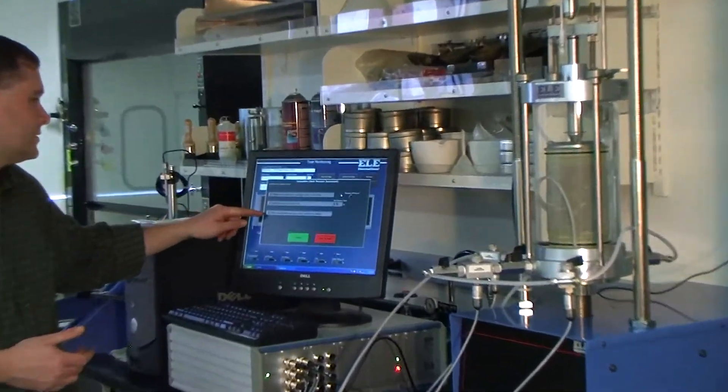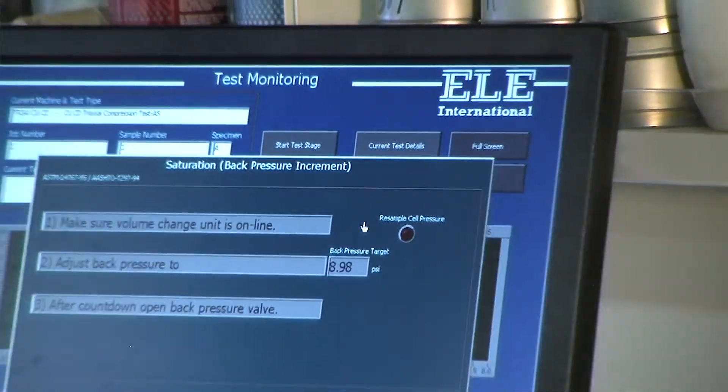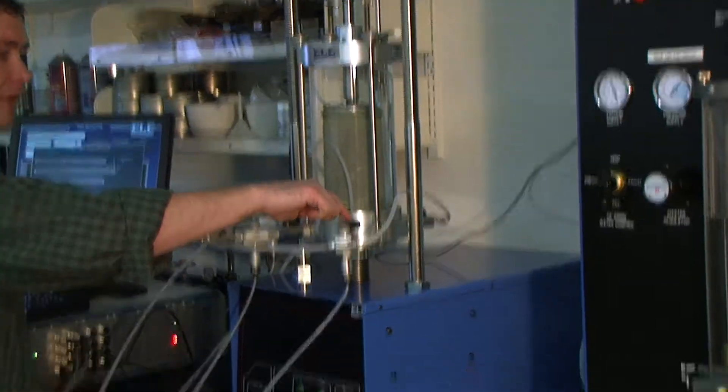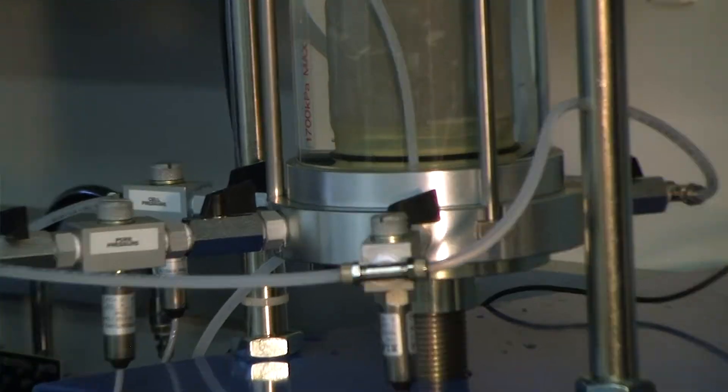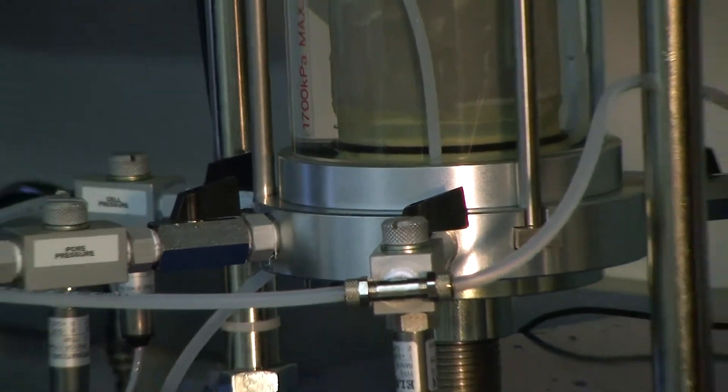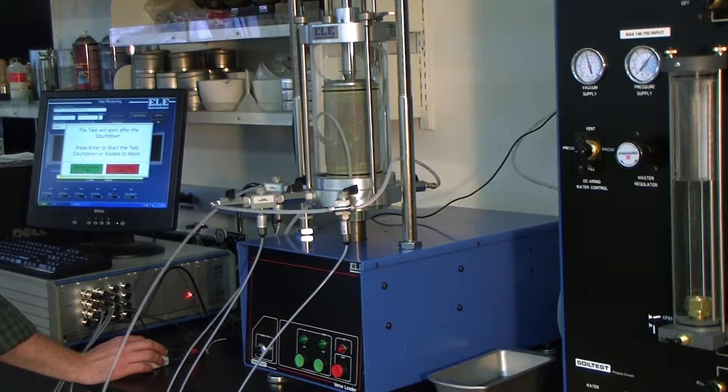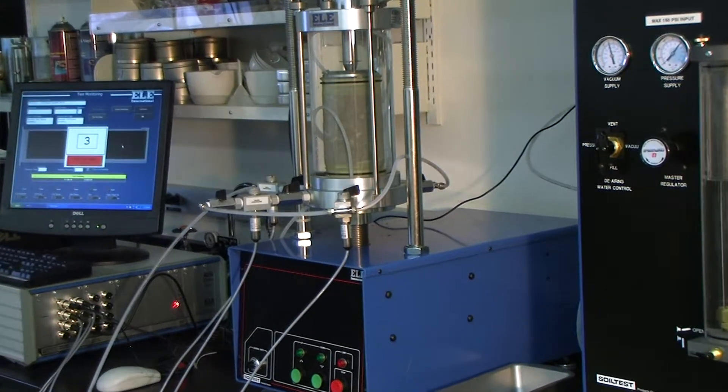So step three is, after the countdown, again a countdown, open the backpressure valve. This is the backpressure transducer labeled right here. This is the backpressure valve. So once the countdown hits zero, open that valve. Hit continue. Start test countdown. 5, 4, 3, 2, 1, then a double beat.